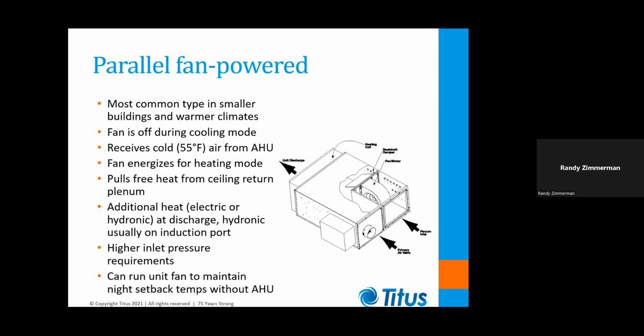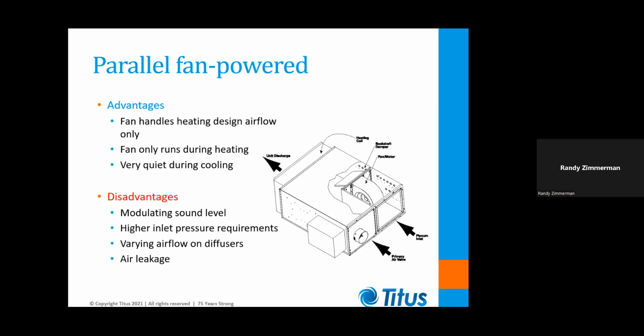Now, of course, this type of box is going to take you back to the higher inlet pressures like you'd have for a single duct VAV box. But let's look at the advantages and disadvantages. Now, the advantages would be that the fan only has to be big enough to handle the heating flow rate. So it could be half the size of the blower in a series fan box. And the fan's only going to run during the heating mode. That makes these units very quiet during the cooling mode.